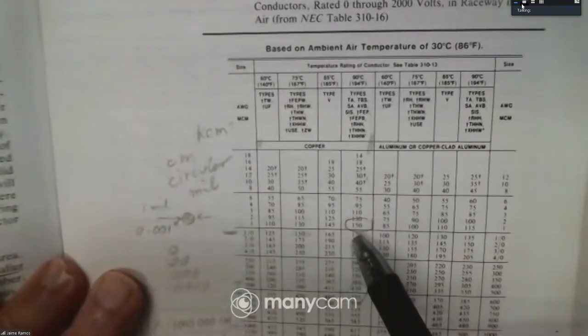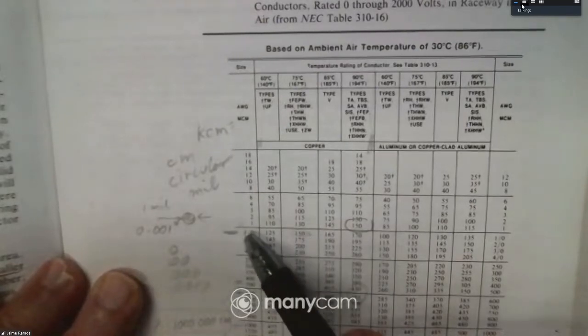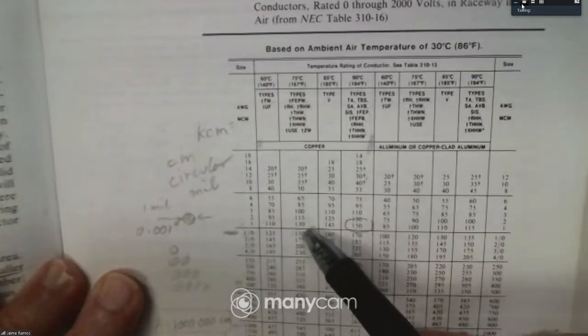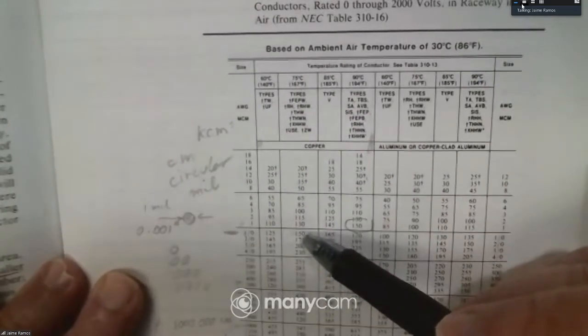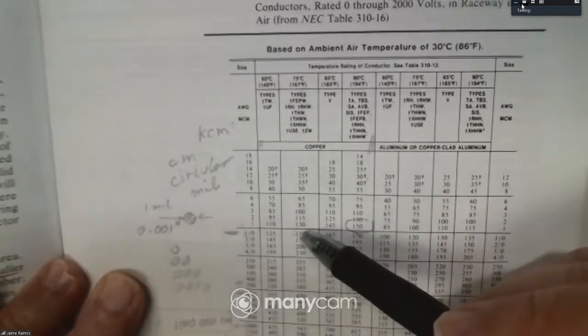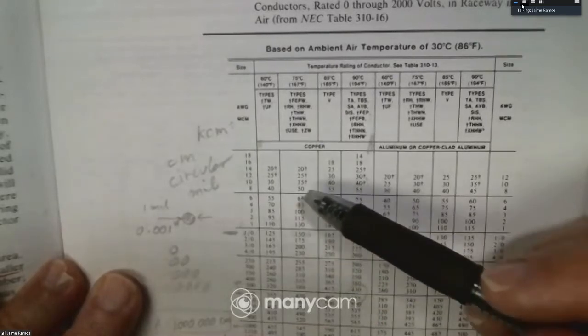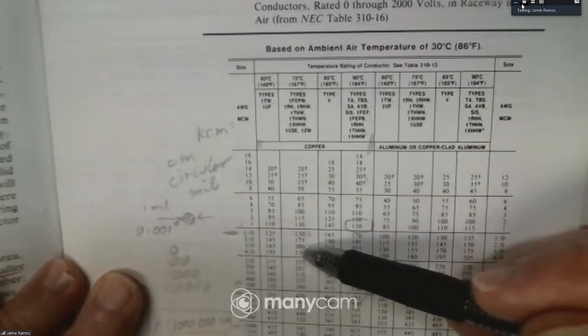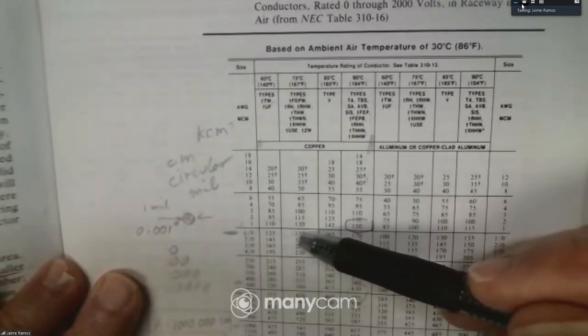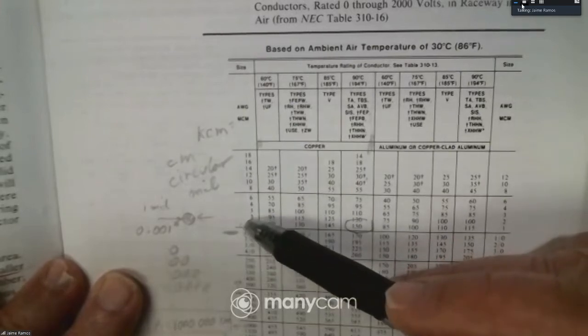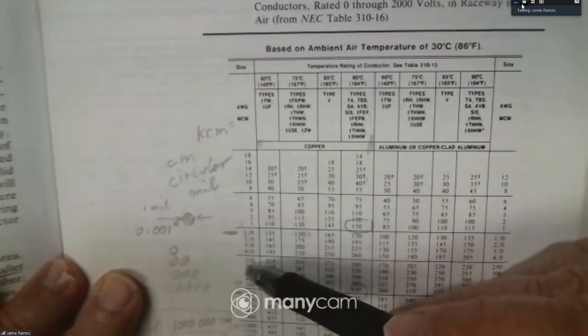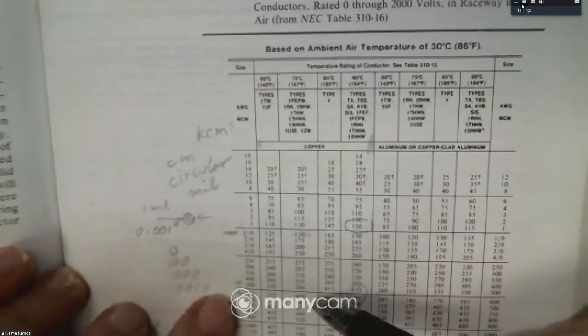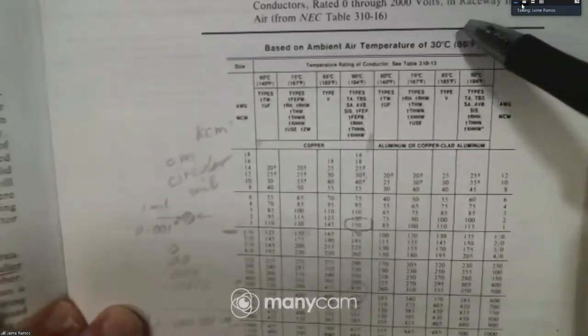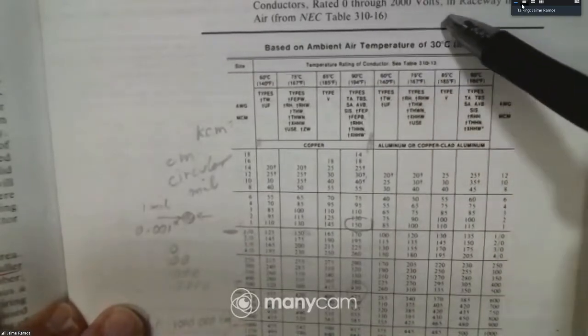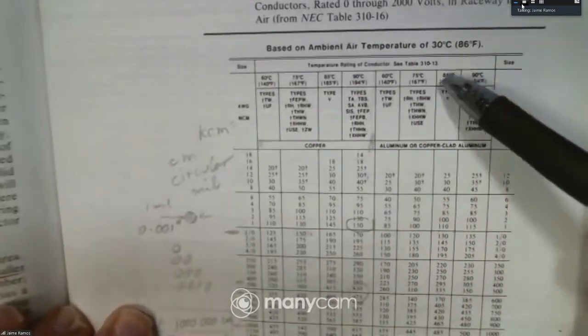Okay. So, for example, 150 amps for cable 1/0 at 75 degrees, the insulation. Okay. So if you require more current, if you require 230 amps, then you move downwards and then follow the increase of the cross-sectional area of the conductor. Okay. Now, all these are good for 30 degrees centigrade. Normal temperature for these are 30 degrees centigrade.